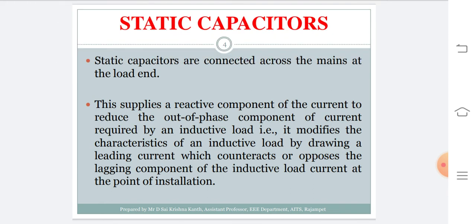By incorporating a capacitor across the load, this capacitor injects the reactive component of current into the system, which in turn reduces the out of phase component of current which is consumed by an inductive load. That is, it is going to modify the characteristics of the inductive load. By injecting this leading component of current into the system, the lagging component of current tends to neutralize, such that it behaves as a normal system.